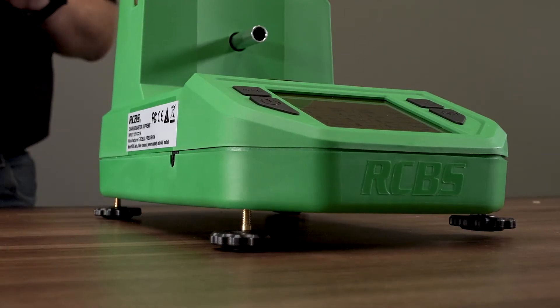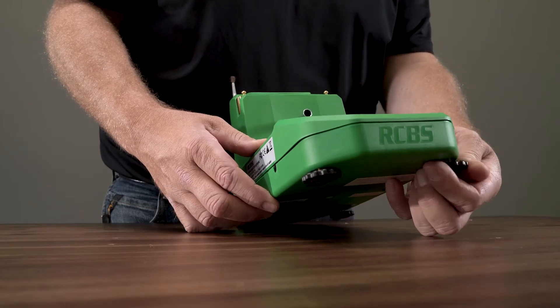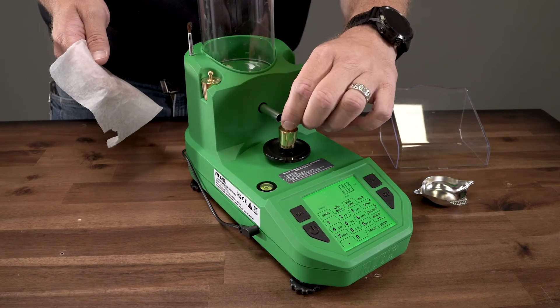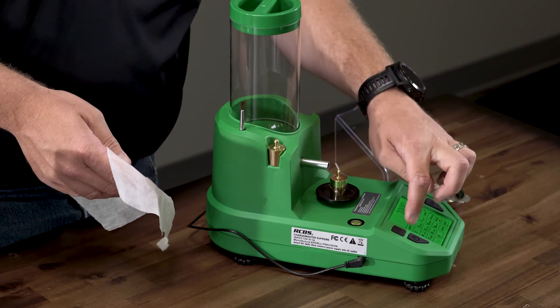Unlevel working surface: you need to ensure your Supreme is as level as possible. Use adjustable feet and the bubble level to ensure the unit is level. Uncentered weight on the platen: all pans and calibration weights should be centered on the platen. This will ensure the weight on the load cell is accurate.